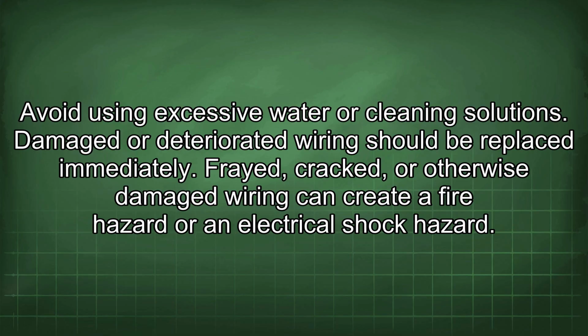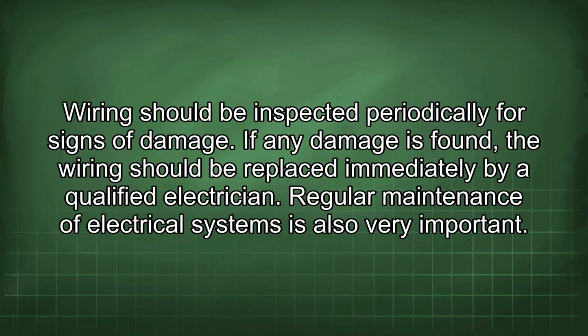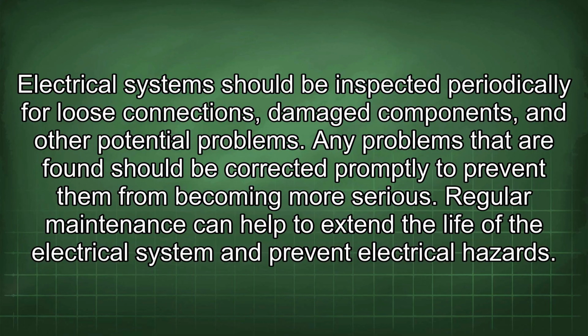Frayed, cracked, or otherwise damaged wiring can create a fire hazard or an electrical shock hazard. Wiring should be inspected periodically for signs of damage. If any damage is found, the wiring should be replaced immediately by a qualified electrician. Regular maintenance of electrical systems is also very important. Electrical systems should be inspected periodically for loose connections, damaged components, and other potential problems. Any problems that are found should be corrected promptly to prevent them from becoming more serious. Regular maintenance can help to extend the life of the electrical system and prevent electrical hazards.